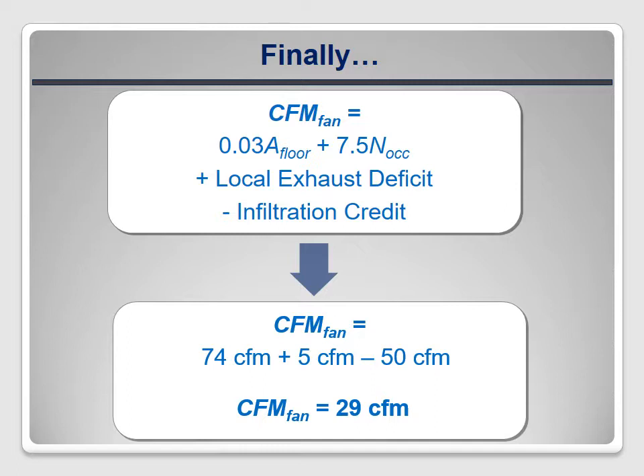One important point: these calculations must be done using a blower door test result after any air sealing is done. But it may be crucial to figure out if a system is needed before the work is done, so it can be included in the work scope and in the quote provided to the customer. Auditors must get good at estimating how much effect air sealing will have on the blower door reading. Be conservative — estimate a small reduction so you don't end up having to install a ventilation fan unexpectedly, possibly at your own expense.